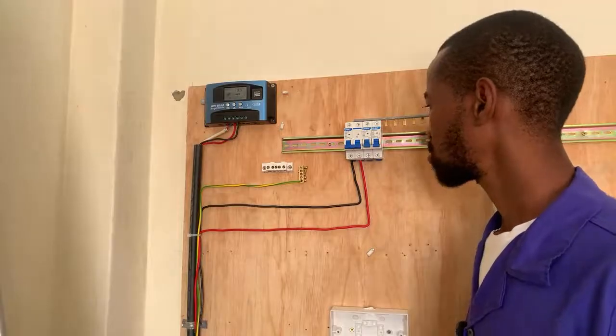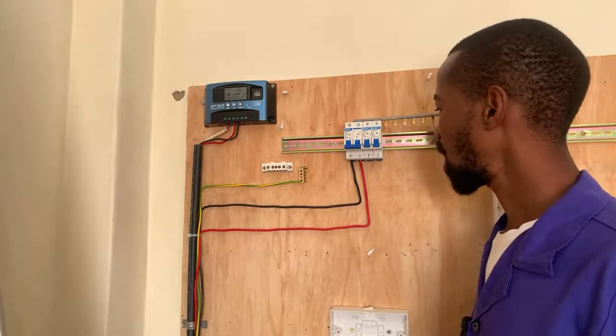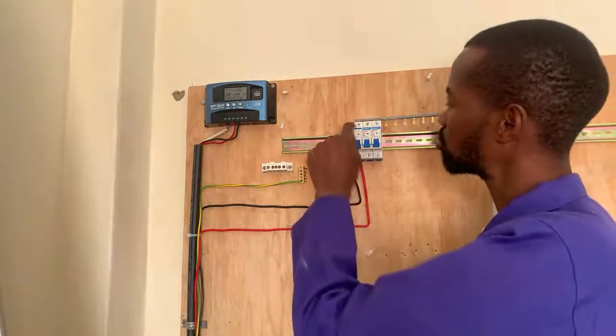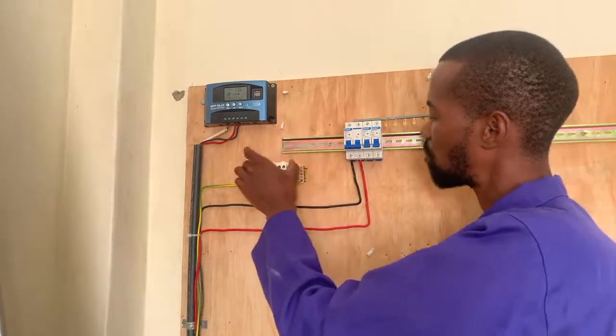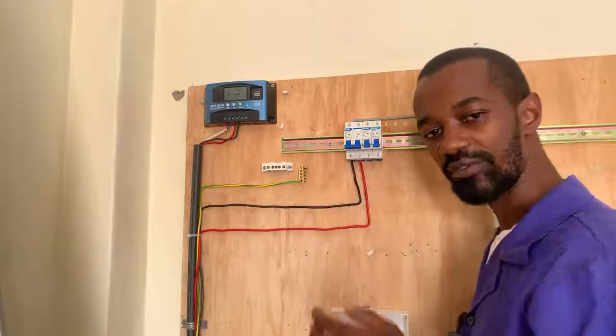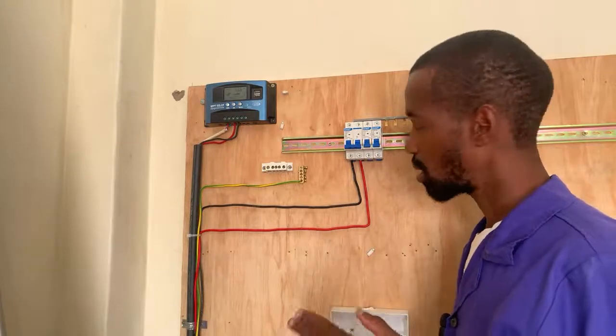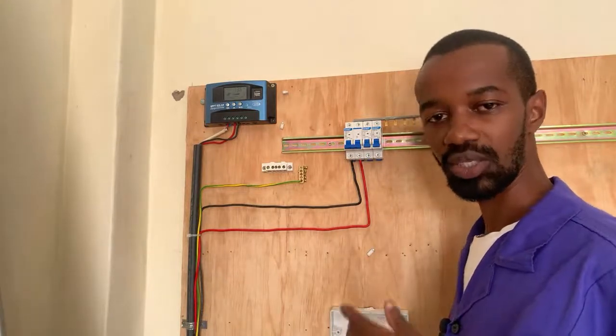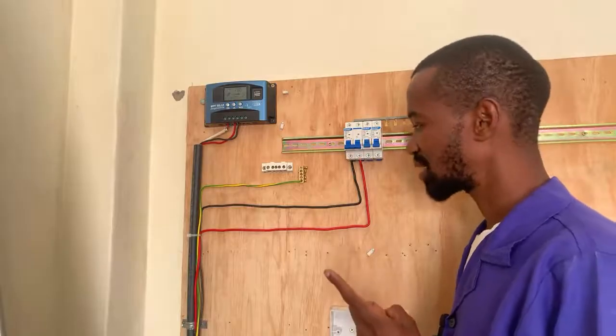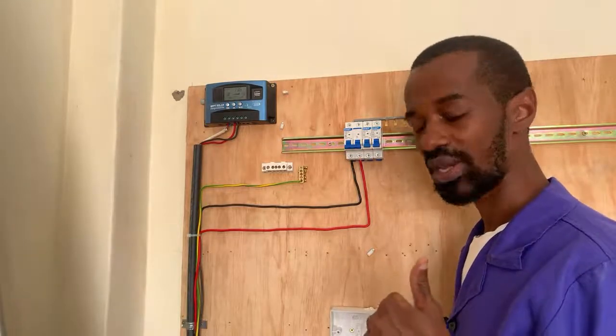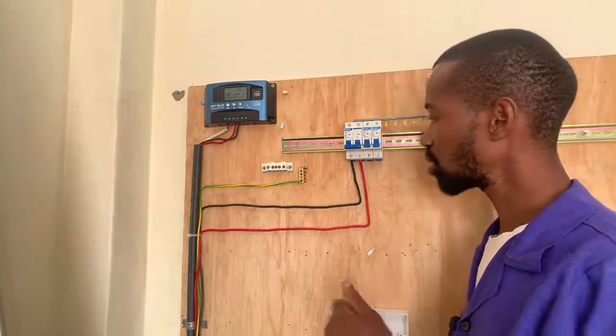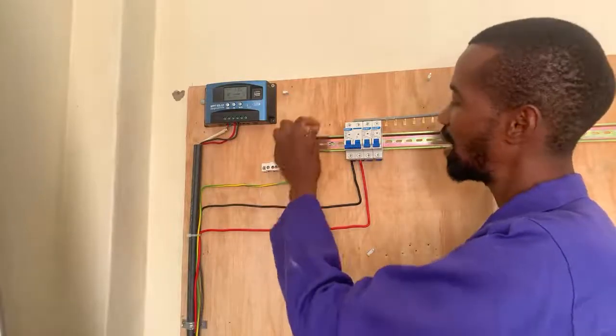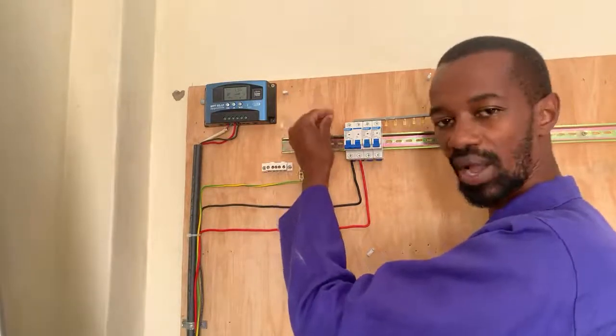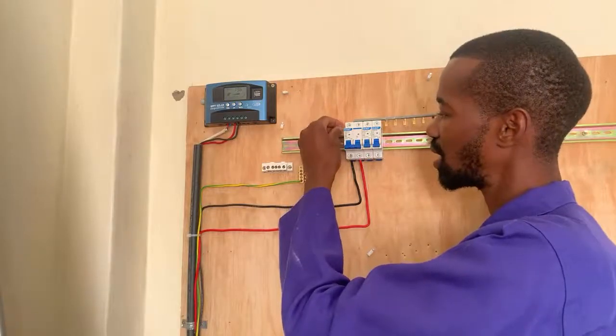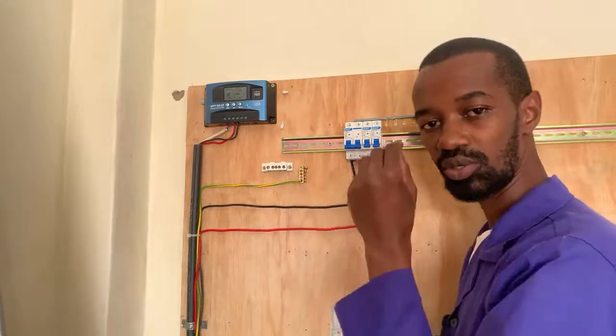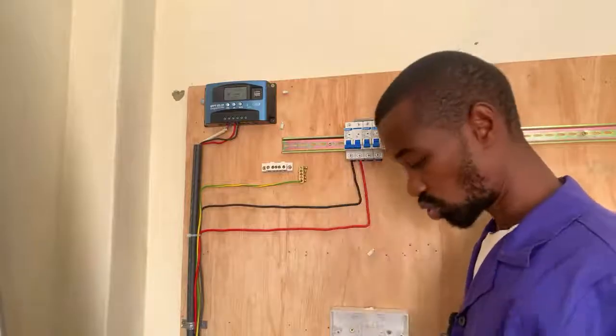So that being said, we now go ahead and connect our neutral from this point to our neutral bar. Like I said in the wiring video I'll post in the description, you must ensure connections are made at the neutral bar, and not clutter the cables going to the circuit, because that will result in a loose connection.